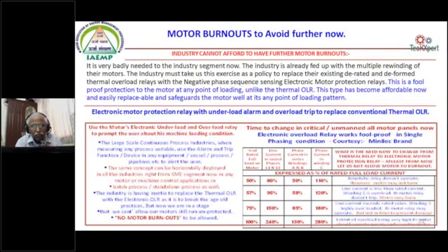The motor burnouts that are happening in the industry, we cannot allow them to happen, because every time a motor burns out and is rewound, there is a loss of almost 3 to 5%. Sometimes it is less than 2%, sometimes it is 5%, depending on the quality of the rewind. Instead of allowing the motor to burn out, we can have electronic motor protection relays. They can work on single phasing, on current unbalance, and on inverse overloading, using negative phase sequence components, as we will see.